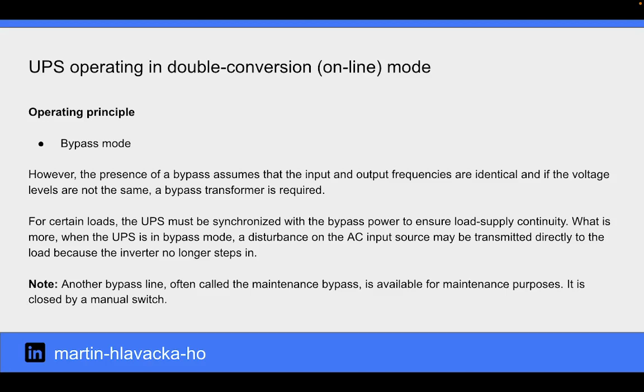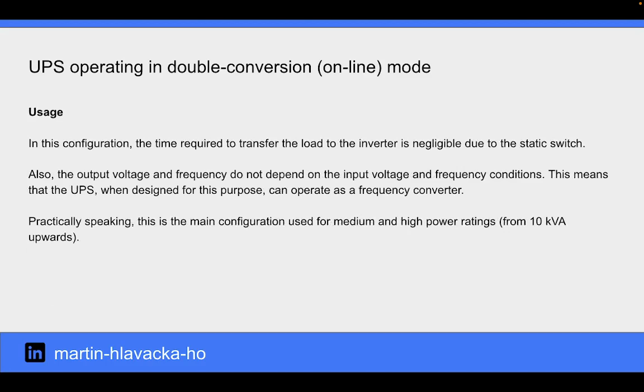Another bypass line, often called the maintenance bypass, is available for maintenance purposes. It is closed by a manual switch. In this configuration, the time required to transfer the load to the inverter is negligible due to the static switch. Also, the output voltage and frequency do not depend on the input voltage and frequency conditions. This means that the UPS, when designed for this purpose, can operate as a frequency converter. This is the main configuration used for medium and high power ratings.